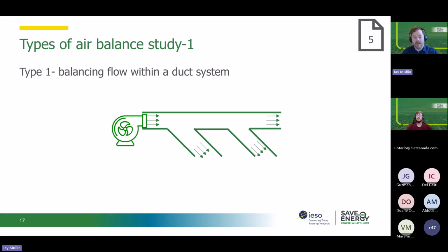And one point on this is that it's very useful to ensure that your air flow systems are working as intended, as designed, but this type of study isn't going to be addressing the building pressurization issues. This duct system could be perfectly balanced at every diffuser and still be leading to negative or positive building pressure because of other aspects or other systems within your building.